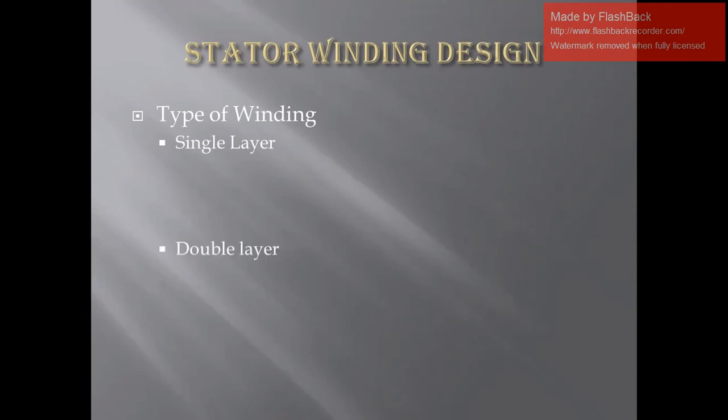In the same way, while designing the stator we have winding design. What type of winding will we follow? It may be single layer type, in which case we use mush winding, or double layer type, where we use either lap winding or wave winding. For a medium size motor we use double layer; for a smaller size motor we use single layer mush winding.